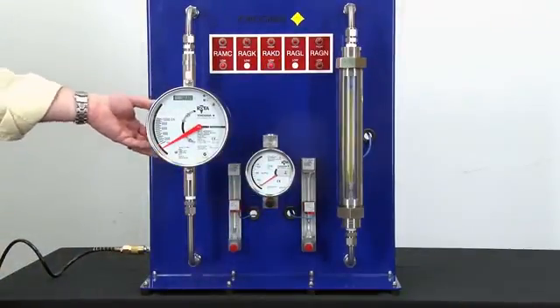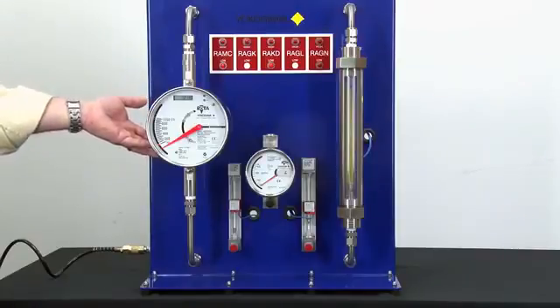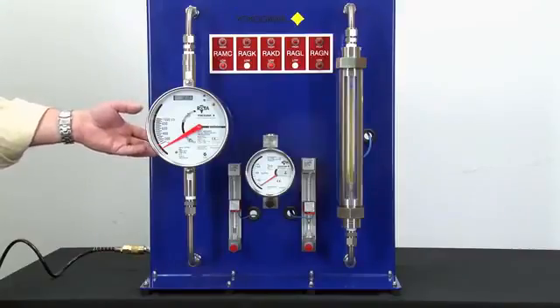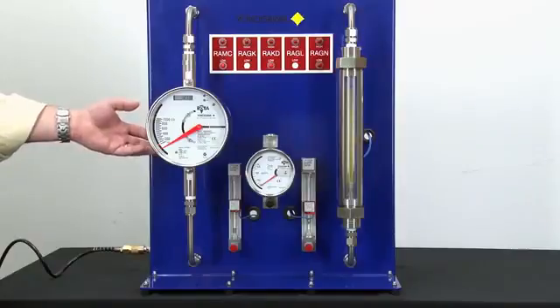Finally, we have the RAMC, the workhorse of industrial flow measurement. Its operating pressure can range from 30 inches of mercury vacuum all the way to 10,000 psi. Its temperature range is from minus 328 degrees Fahrenheit to almost plus 700 degrees Fahrenheit.